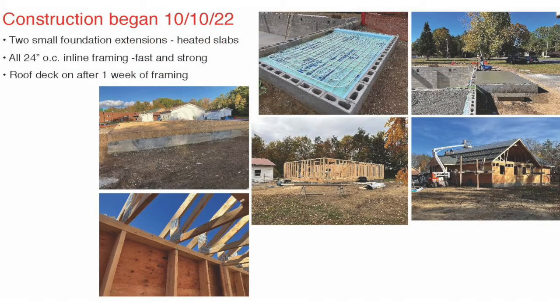Again, we added a couple small areas here in the upper middle. You can see we added a vestibule. It's a small area, only 8 by 12 feet, but we decided to do floor heating in there. So we tied in two small areas of slab-type radiant floor heating with 10 panel radiators. And we designed the system so it all operates at one water temperature. We don't have to have mixing involved.